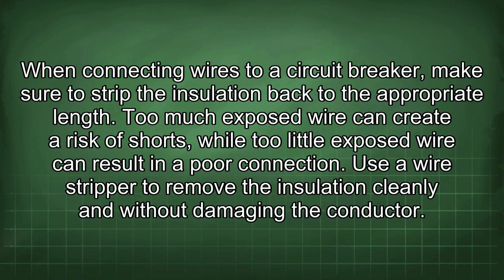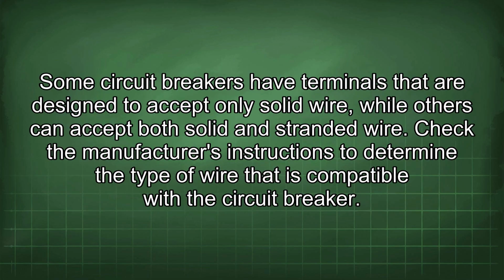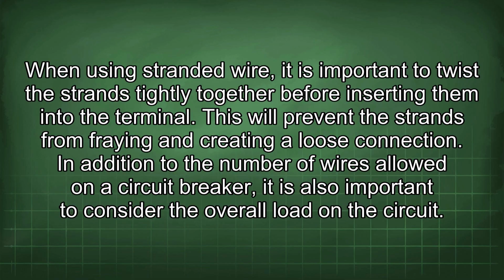When connecting wires to a circuit breaker, make sure to strip the insulation back to the appropriate length. Too much exposed wire can create a risk of shorts, while too little exposed wire can result in a poor connection. Use a wire stripper to remove the insulation cleanly and without damaging the conductor. Some circuit breakers have terminals that are designed to accept only solid wire, while others can accept both solid and stranded wire. Check the manufacturer's instructions to determine the type of wire that is compatible with the circuit breaker. When using stranded wire, it is important to twist the strands tightly together before inserting them into the terminal. This will prevent the strands from fraying and creating a loose connection.